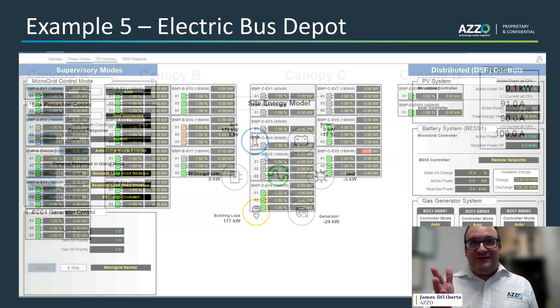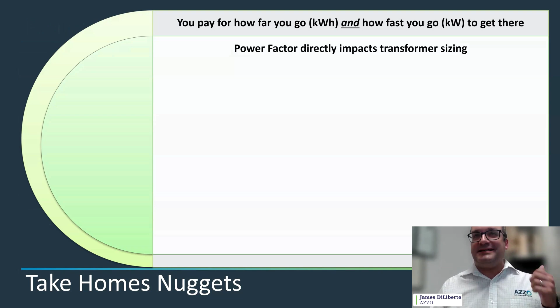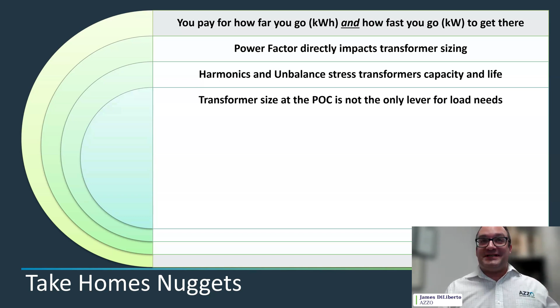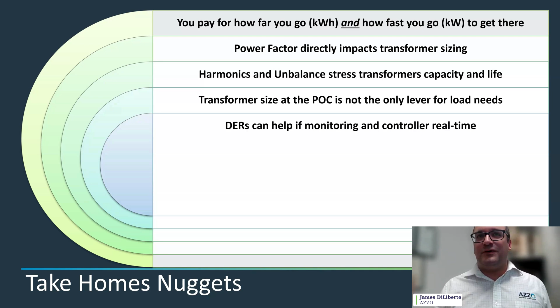So let's take it home. Some nuggets I hope you learned: first, you pay not only for how far you go - the cumulative distance in kilowatt hours and energy - but also how fast you go, kilowatts to get there, or kVA in transformer capacity. Power factor directly impacts transformer sizing, and that can be addressed. Power quality themes like harmonics and unbalance can also stress transformer capacity and lifespan. Transformer size at the point of connection is not the only lever for load needs. DERs, as Stace will mention shortly, can obviously help - we had some examples of that before, and Stace will talk more about it.